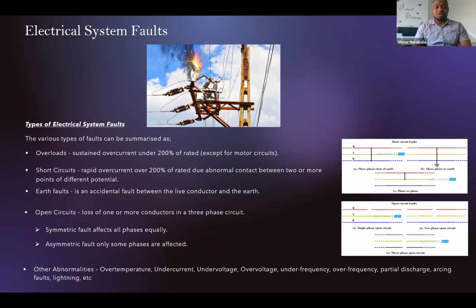We also have open circuit, sorry. Open circuit is where we lose a phase of a balanced three-phase supply, where all of a sudden the system becomes unbalanced. In some cases, we experience this where we have mechanical damage and a cut on a power cable, or we have a sudden fuse blown on a three-phase line. And as a result, we have an imbalance in the system. So as a result, we get an open circuit fault.